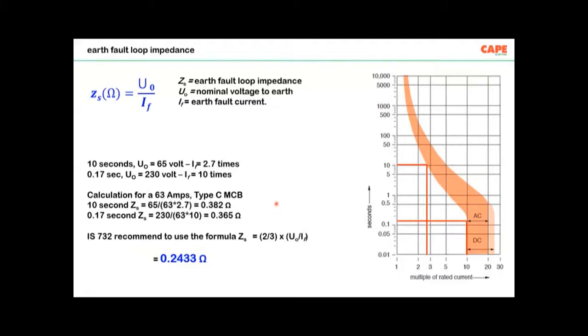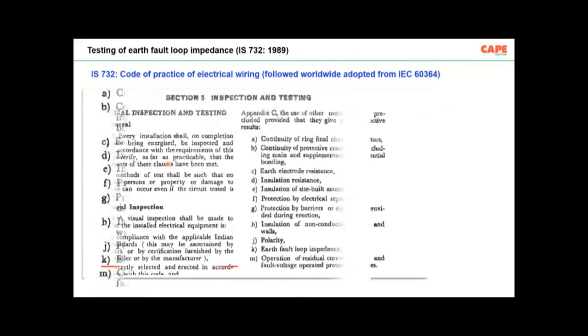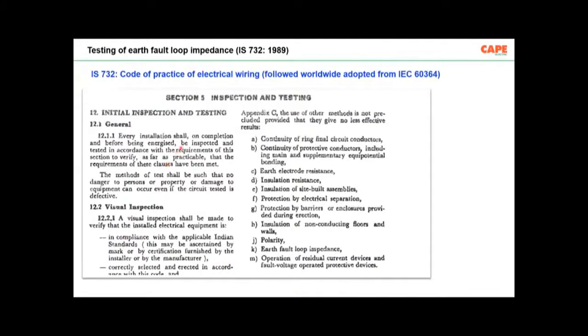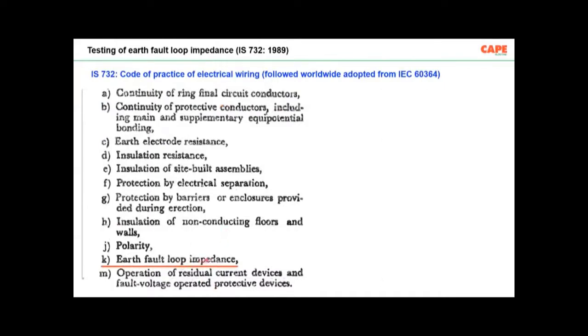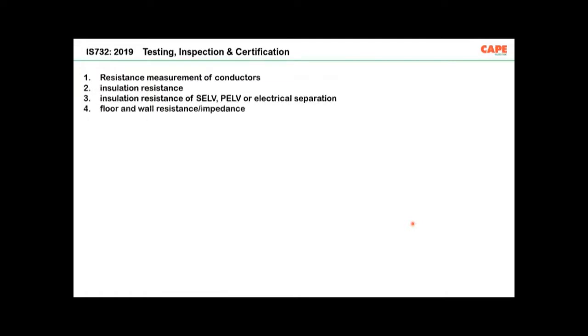Now, for disconnecting your MCB within this time, the fault loop impedance is very important, which is recorded in several standards. What I am showing is IS 732 1989, a very old standard, 32 years old. You see here, section 5 of this standard talks about earth fault loop impedance testing. So this parameter was included in the standard approximately 30 years back, but even today, very, very few installations do this particular testing.